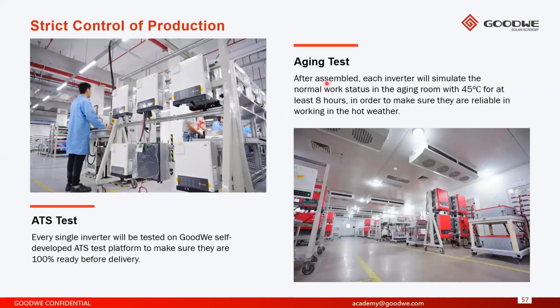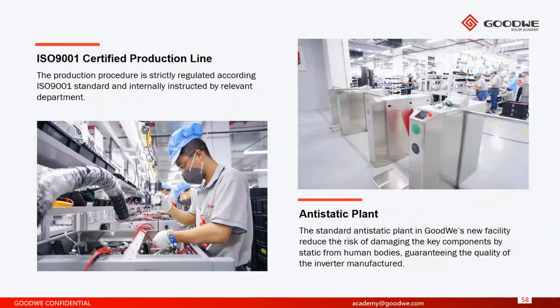We go through a number of other aging and ATS tests on the inverter. As you can see here, on the right-hand side, this is the aging or ATS test that we put our inverters through, and this room is run at a particular temperature. I think it's 40 to 50 degrees, and it's at a high humidity. We run the inverters at 100% output, and we go through a number of tests of this type. Our production line is certified for ISO 9001. So we have a number of strict quality control procedures and processes in place to ensure that the inverters are manufactured to the specification that we require.